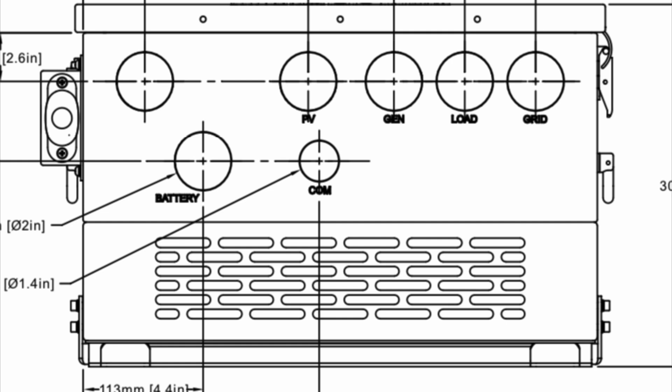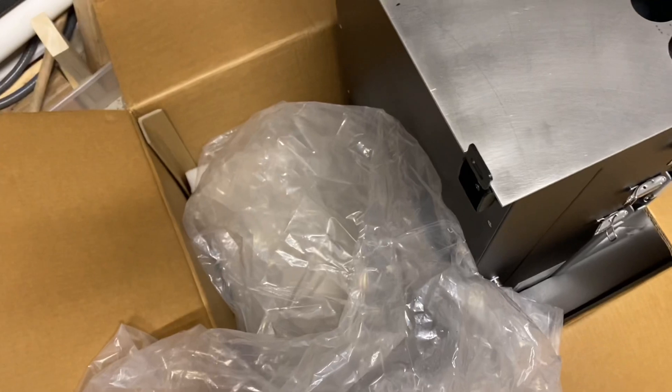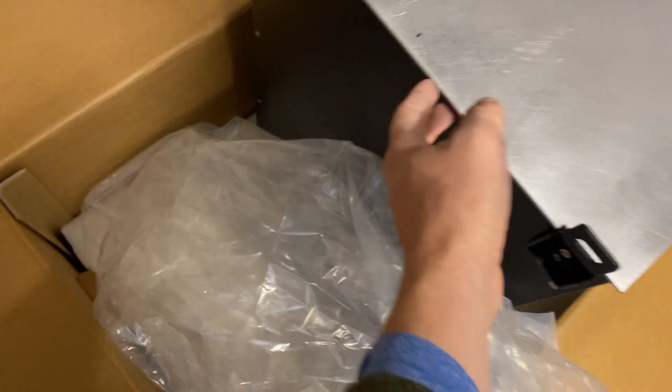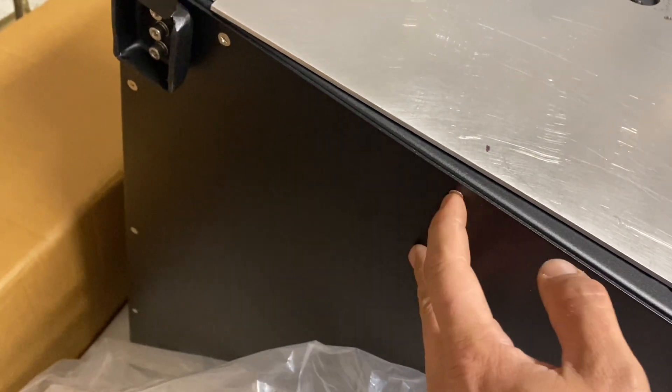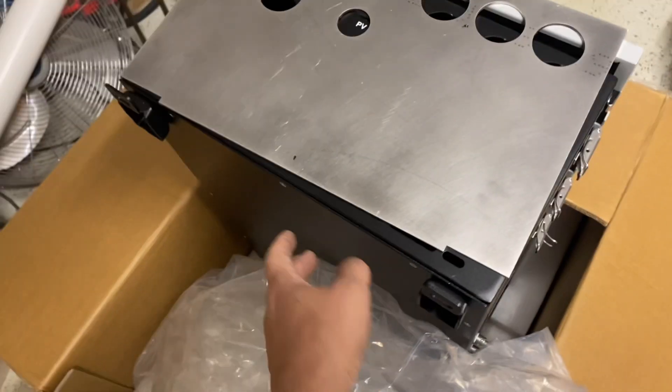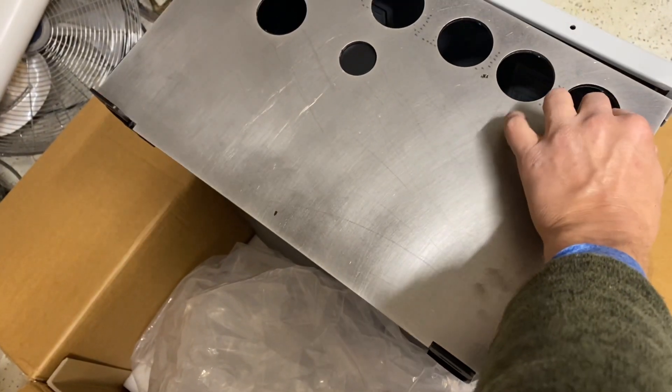There are six 1.5-inch knockouts. You want to get 1.5-inch EMT TAs, and there are six knockouts on the bottom of the Sol-Ark. On the 15K, you're going to want to find the exact center. This little screw on the bottom is very close to the exact center — you can use that as a reference point, but you might want to verify it each time.